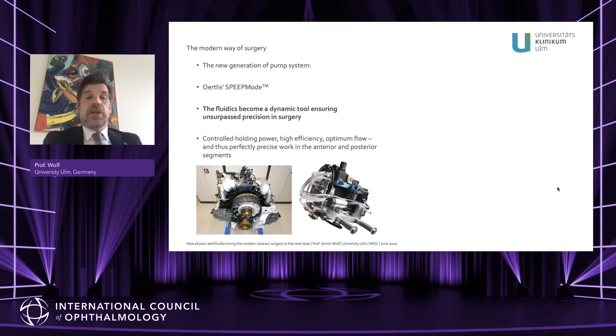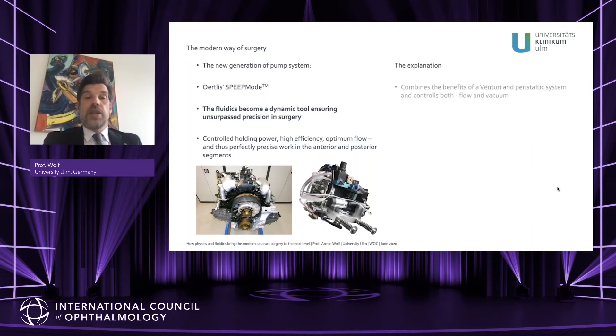By using the SPEEP mode, it allows you a controlled holding power, very high efficiency, an optimized flow, and thus perfectly precise work in the anterior as well as in the posterior segment. The explanation for this high efficiency is that the combined SPEEP mode combines the benefits of a Venturi-based system and the peristaltic system, controlling both the flow and the vacuum at the same time.